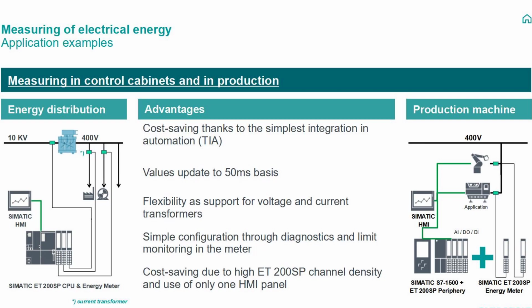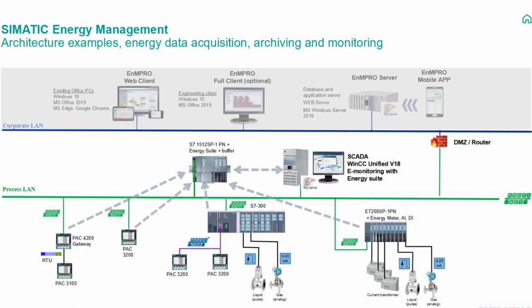Energy meter placement is a critical aspect of power metering and is determined by the specific use case and requirements of the facility. Factors such as the type and size of the facility, the number of energy consumers, and the desired level of granularity in the energy consumption data will all impact energy meter placement. In the example here, one could see that the ET200SP energy meter could easily be used in either energy distribution or production machine environments. By aggregating energy data at a controller level, facilities can gain a more comprehensive view of energy consumption and identify areas for improvement.